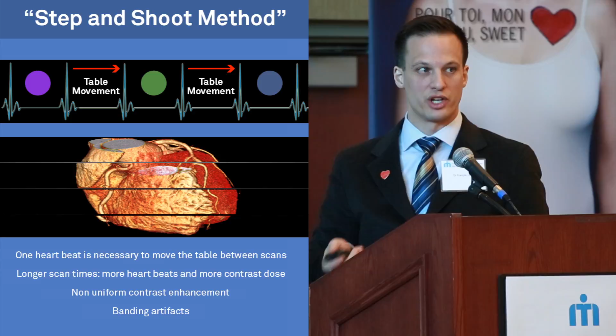So CT or MDCT, multi-detector CT, evolved. At first it was 4 detectors that covered about 2 millimeters, evolved to 16 detectors, 64 detectors, which is what Montfort currently have and a lot of hospitals do. This is what was most commonly used to do this step and shoot method or stitching method, and that covered about 3.2 centimeters. There was an 80 detector that came out a few years later, but not significantly different from the 64 detector. Well, the technology that Montfort is going to acquire, or this Toshiba Aquilion 1 CT, has 320 detectors. So that's 16 centimeters.